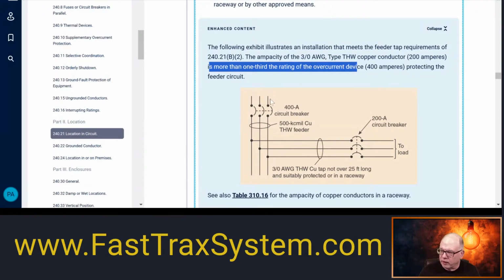So this is a 400, and this was a feeder, right? So this is where other people get confused. They go, that's a feeder. Wait a minute. You said that you didn't have... We weren't talking about the tap conductors now. We're talking about the feeder itself first. And yes, this is a 500 kcmil copper, which we saw is good for 380 amps, terminating on a 400 amp overcurrent device, because this is using the what? 240.4. This isn't a tap conductor. This is the feeder, right?